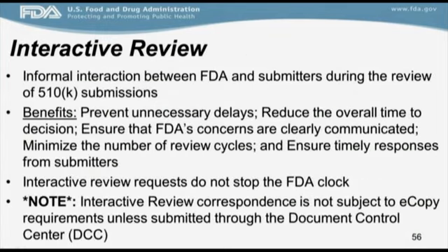Interactive review is an informal interaction between FDA and the submitters during the review of your 510K. Interactive review requests do not stop the FDA clock. That can be very beneficial because it prevents unnecessary delays, it may reduce the overall time to decision, and it ensures that timely responses from submitters are received. The reviewer will determine whether or not interactive review is appropriate. Please note, though, that interactive review correspondence is not subject to e-copy requirements unless you submit information needed for the interactive review through the Document Control Center. Anything that is submitted to the Document Control Center must have a valid e-copy.